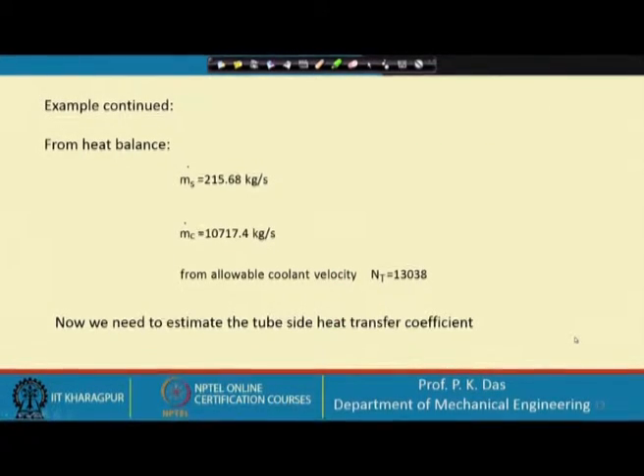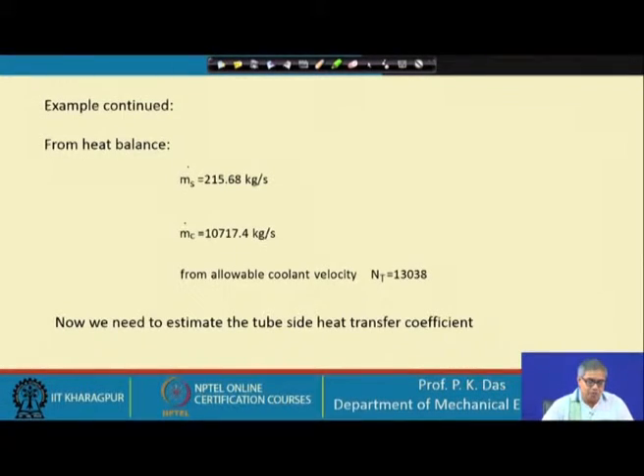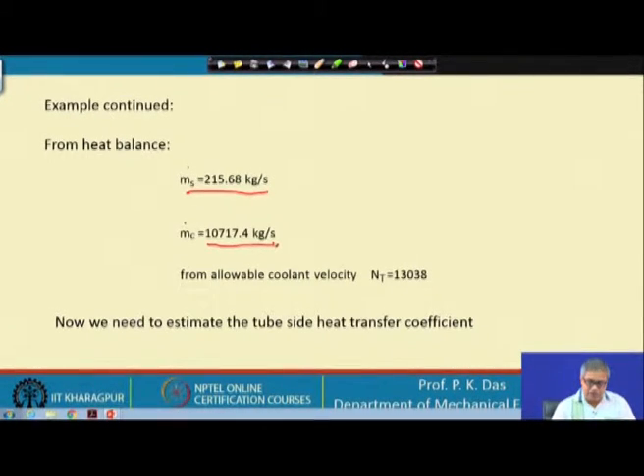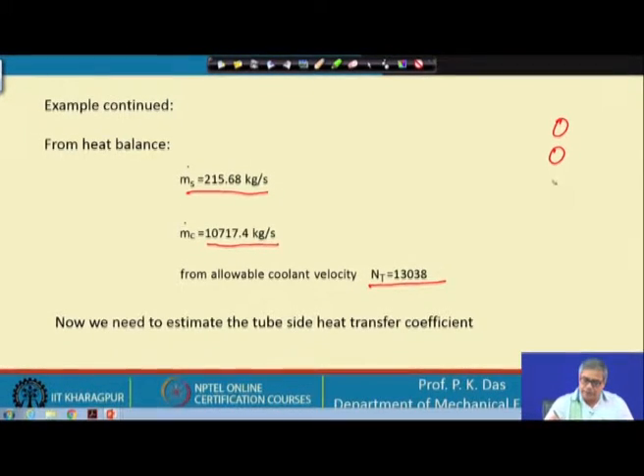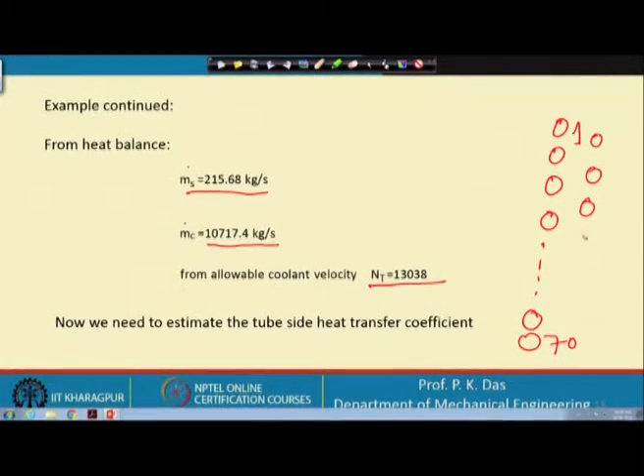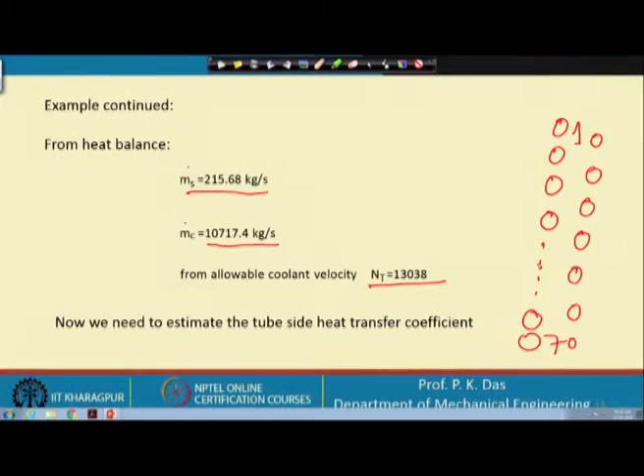Here you see the example we are continuing. From the heat balance we have got two very important quantities: the steam flow rate m-dot-s, and the total rate of heat transfer. From the allowable coolant velocity we have got N_t, the total number of tubes. We have assumed that on a column there will be 70 tubes.